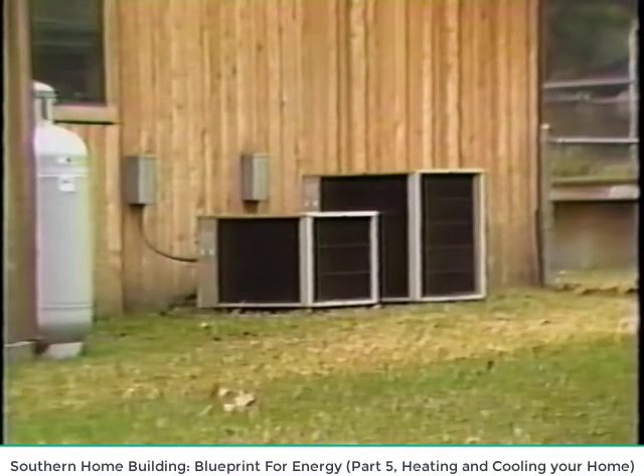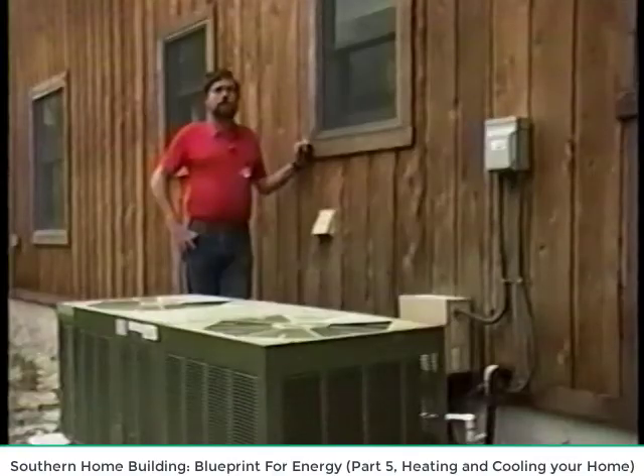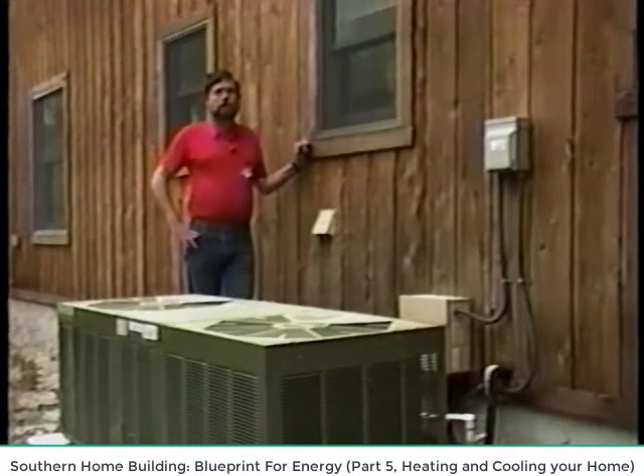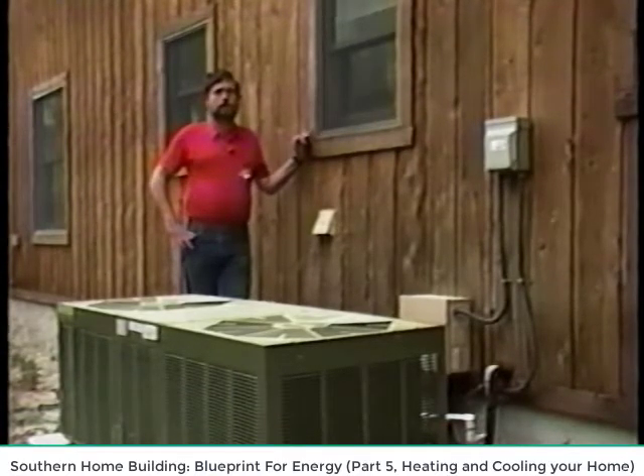In nearly all cases, a two-zone motorized damper system with just one heat pump plus larger capacity duct costs less than a two heat pump system. This is a 3,800 square foot, two-story house which received bids for up to 6 tons of cooling using 2 heat pump systems. By installing motorized dampers, we were able to install 1 4-ton heat pump. This particular house has 4 zones using thermostats in each zone for comfort. The customer has been very pleased with its operation and the equipment has performed excellent.